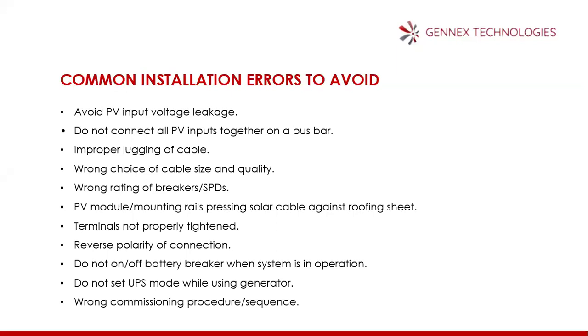Please avoid PV input voltage leakage, which means you have to test for leakage and be sure there's no leakage in your PV line. Do not connect all PV inputs together on a bus bar. This is a high voltage system. Let every string go straight to the input provided on the inverter. Improper cable lugging can damage the inverter. It can damage cables, can cause fire, can cause anything. So please avoid this mistake.